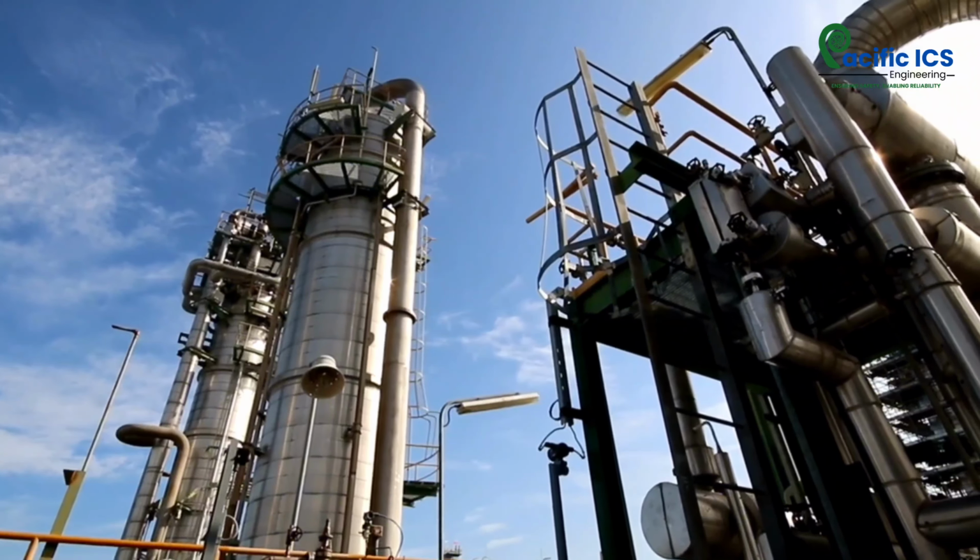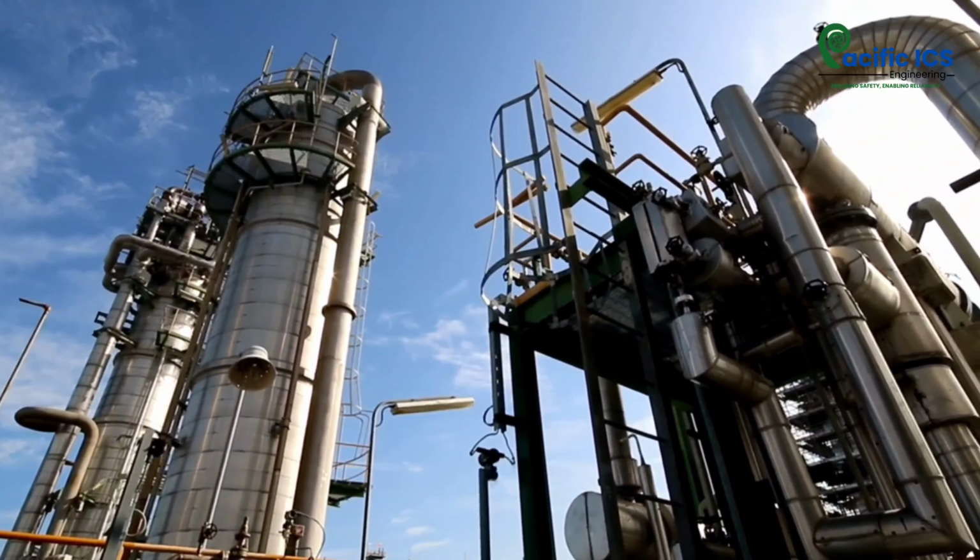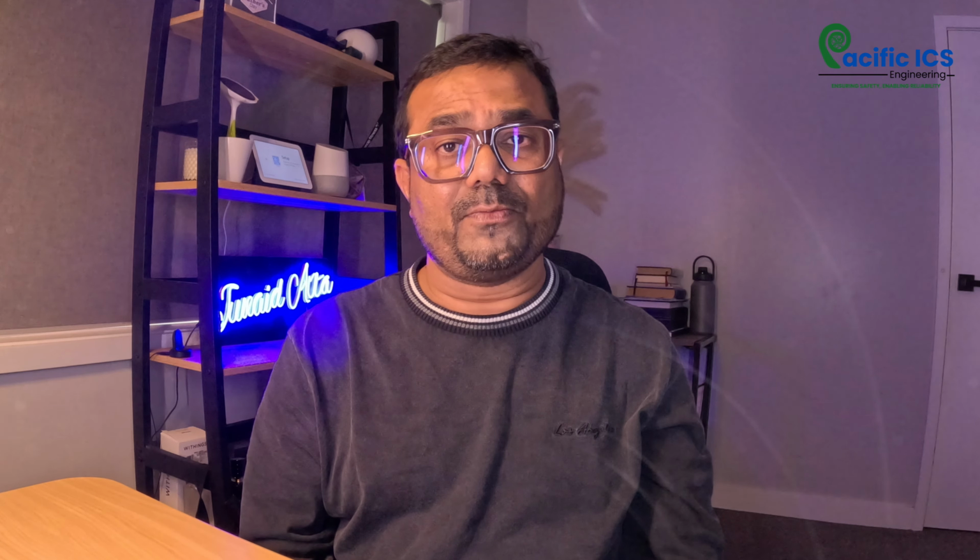All right, the gear is on site, but this isn't plug and play. Now we validate installation and integration. SAT, or site acceptance testing, checks the complete loop after installation: wiring, I/O signals, logic sequences, and control responses. It confirms all connections are correct and working. We energize the transmitter, simulate high pressure, and check the valve shuts in exactly 2 seconds, not 2.5, not around 2. The system must respond exactly as designed and documented. If FAT proves components work, SAT proves they work together in the real world. Don't skip, don't assume.